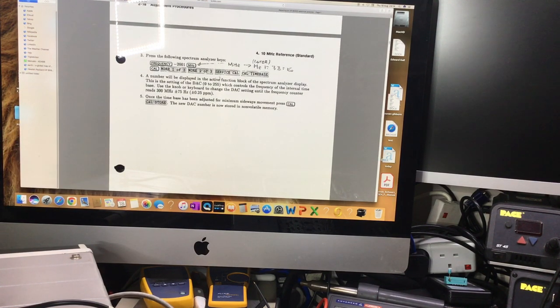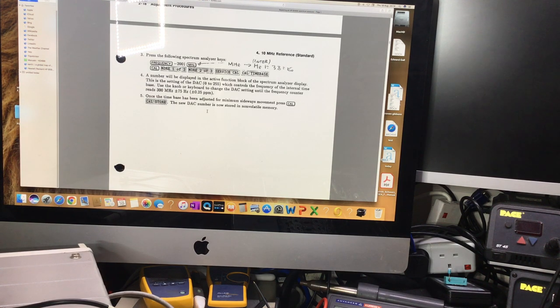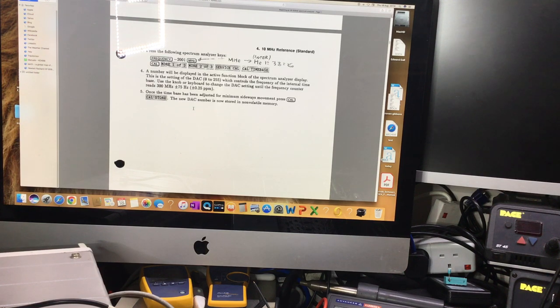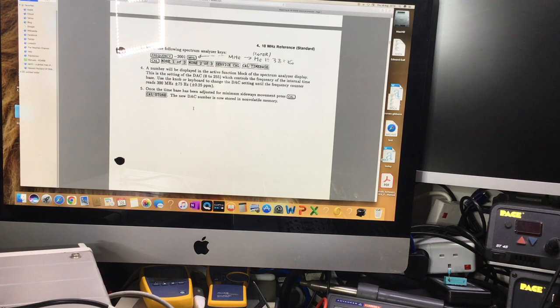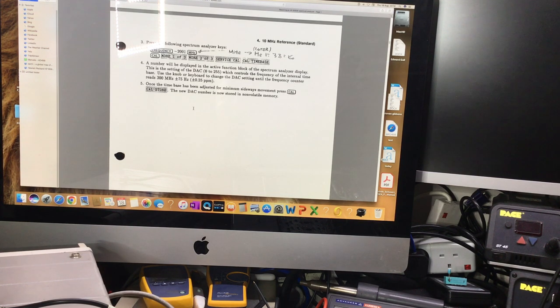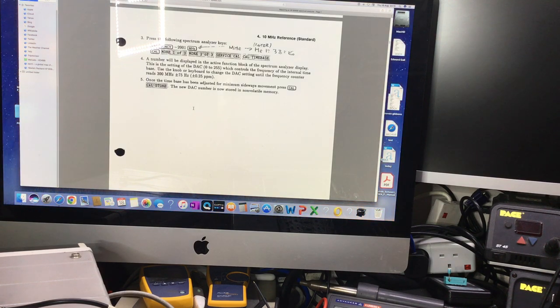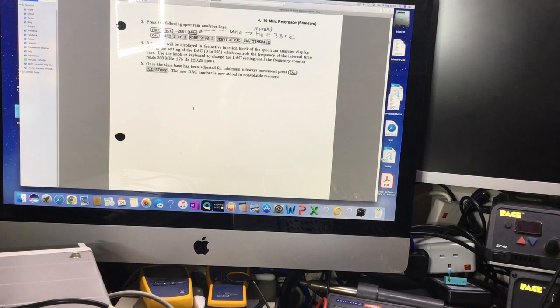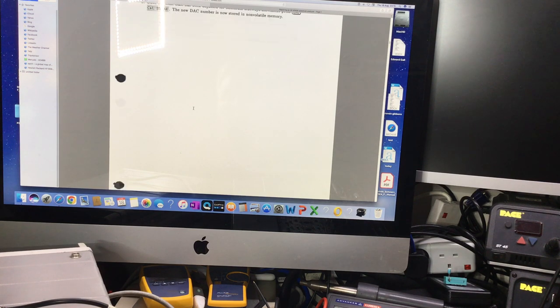We put this code in, we've now got a DAC displayed on the screen, and then it says a number displayed in the active function block of the Spectrum Analyzer display. This setting is DAC 0 to 255, which controls the frequency of the internal time base. Use the up or down keys to change the DAC setting until the frequency counter reads 300 megahertz plus or minus 75 hertz, plus or minus 0.25 parts per million. Once the time base has been adjusted for minimum sideways movement, press cal store. The new DAC number will be stored in non-volatile memory.